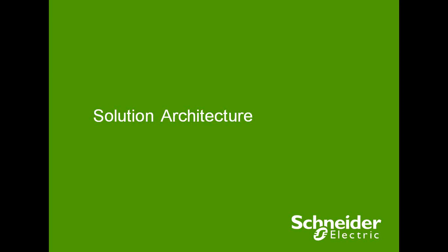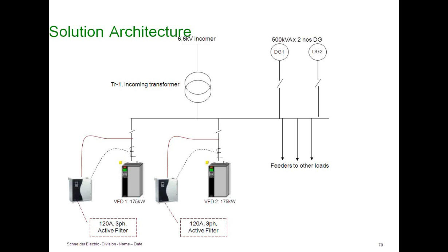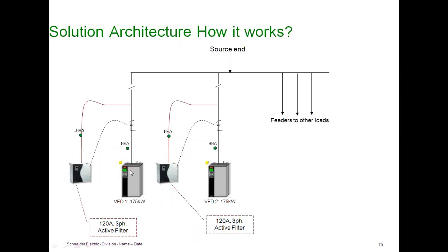So the solution was to have an active harmonic filter at each drive. So the drive will generate some harmonic current, and the active filter senses the harmonic current from the drive and will cancel it out at the input side. And the net harmonic current flowing in the generator will be sum of 0. So it's been done. Now the generator is working without any tripping. The generator is working for the past 3 to 4 months, not even a single trip, after cancelling harmonics in the system.